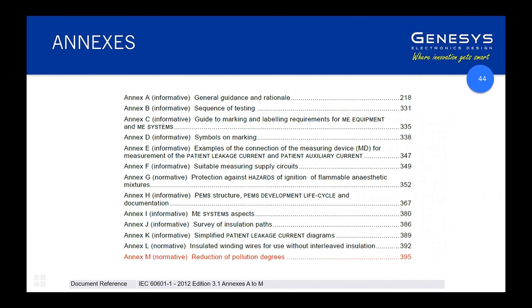Finally, the standard has a range of annexes, most of which are informative — meaning you don't need to comply with them — but there are a couple of normative ones, including one recently added. It's well worthwhile working through these annexes and becoming familiar with them, as they give a lot of explanatory information about the intent behind the clauses and tests you need to comply with.